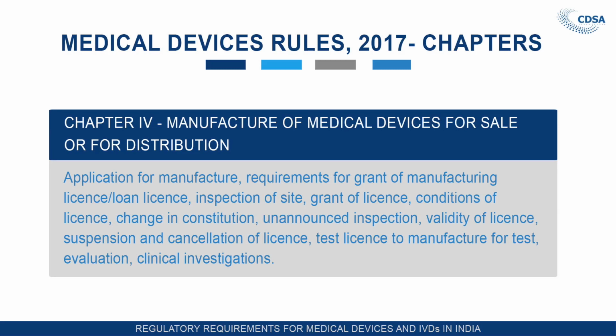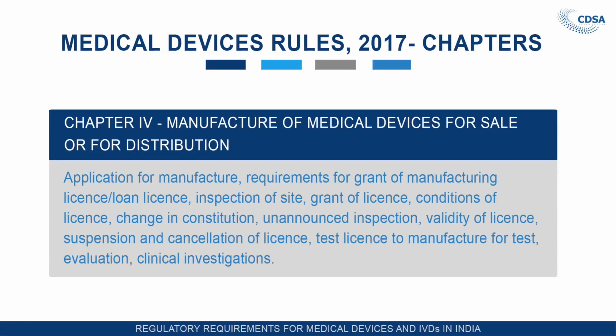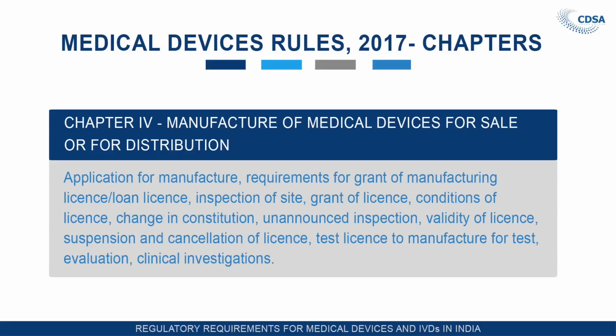The state licensing authority will inspect the premises of class A and class B devices which have already been recommended by the notified body for grant of a manufacturing license. Two percent of those manufacturing units will be audited by the state licensing authority through unannounced inspection. Also covered are the validity of the manufacturing license, provision for suspension and cancellation of the manufacturing license, and the test license to manufacture test batches for test evaluation or clinical investigation of medical devices and in vitro diagnostic kits. That provision has been included in Chapter 4. So the procedure for grant of a manufacturing license, conditions of the license, suspension, and validity of the license have all been made in Chapter 4 of the Medical Device Rules 2017.